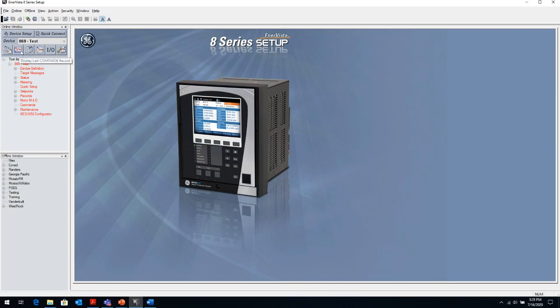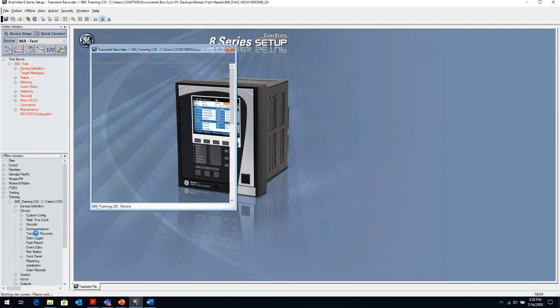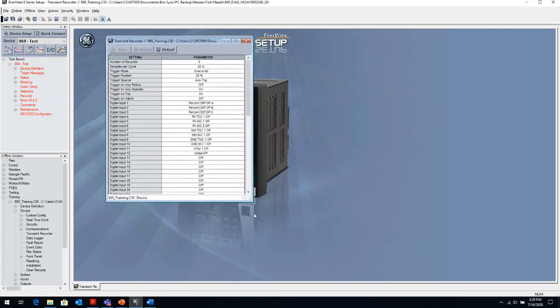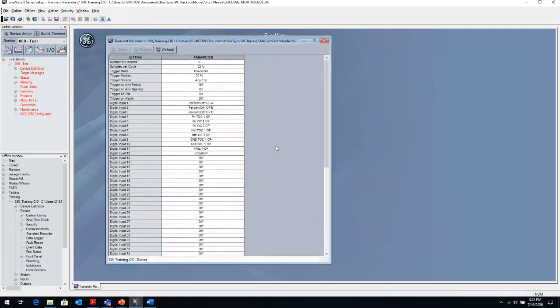The next one over is the oscillography. The oscillography is basically a COMTRADE, so that's a snapshot of the power system that was captured during some sort of disturbance, whether it's a trip. But you, as a user, have to set up this oscillography trigger. And it's very important, so I want to show you that. It's very important to set up that oscillography trigger so that it captures what you need it to capture. So by default, it will capture all the currents and voltages that are available in the relay.